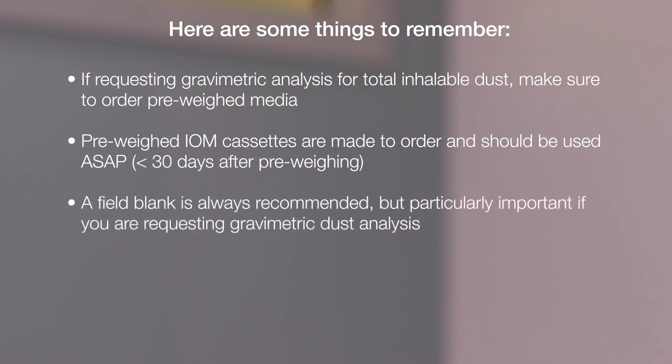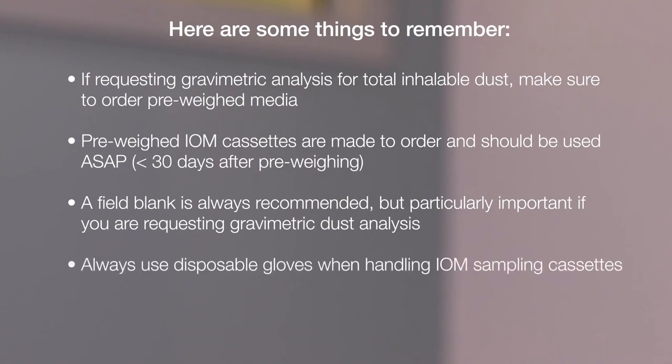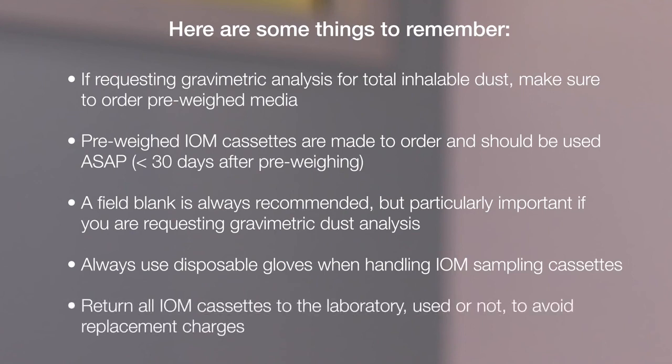A field blank is always recommended, but particularly important if you are requesting gravimetric dust analysis. Always use disposable gloves when handling IOM sampling cassettes. And return all IOM cassettes to the laboratory, used or not, to avoid replacement charges.